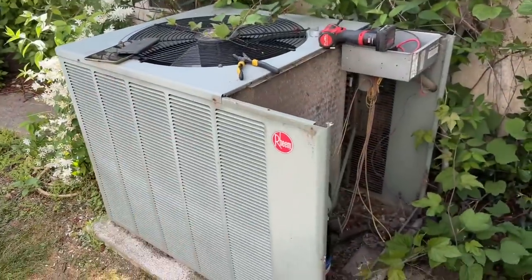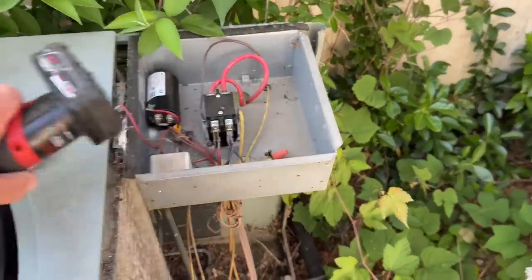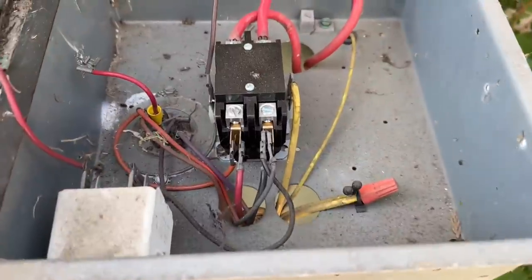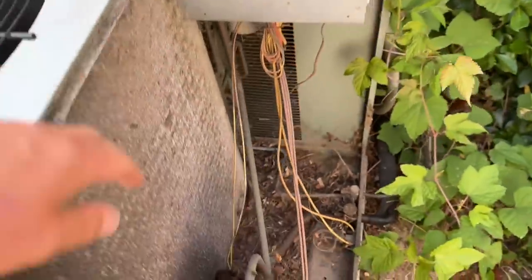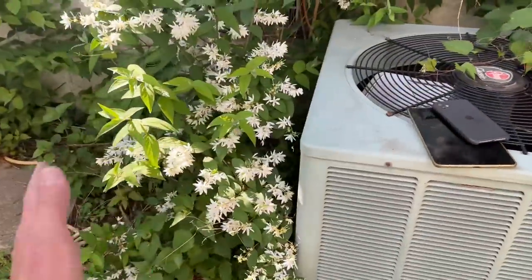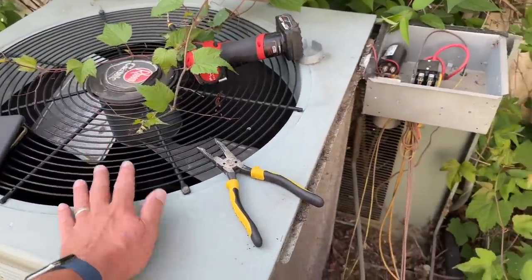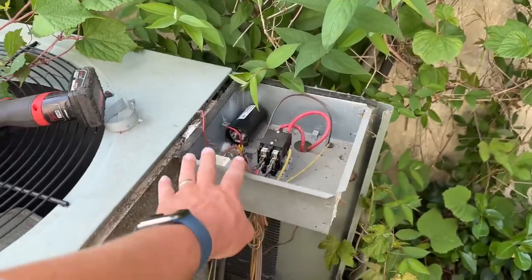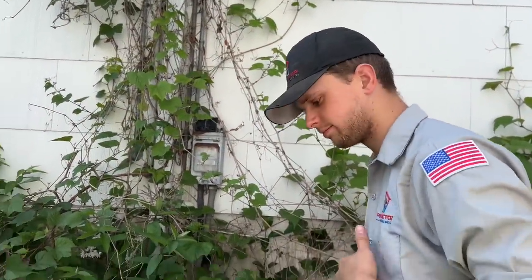We haven't been here in three years to do service. Number one, we have this extra capacitor which was leaking oil right here. This capacitor was replaced three years ago but she's still leaking. The inside coil looks brittle and it is. We have a lot of debris inside and a lot of vegetation overtaking the area. We're going to bring this behemoth of an R22 system back to life.